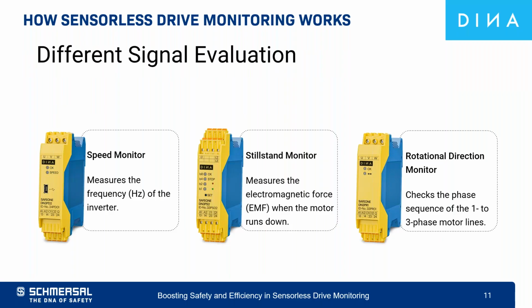In 3-phase motors, the order in which the 3 phases U, V and W, or L1, L2, L3, are connected determines the direction of rotation. The rotational direction monitor module analyzes the phase sequence of the supply current. This ensures that the motor only rotates in the intended or safe direction, which is a vital safety requirement to prevent risk. This is the technical explanation about our sensorless modules.